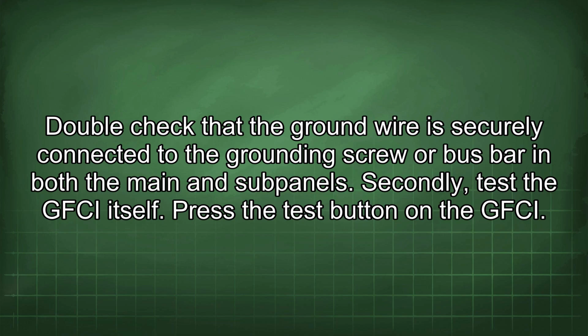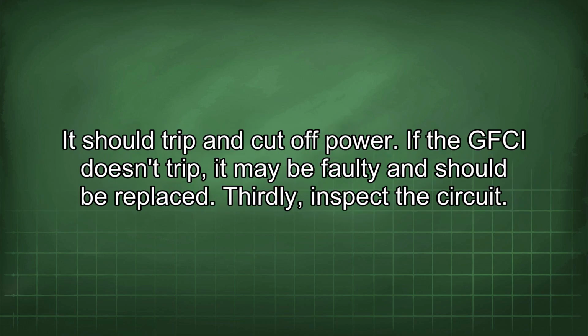Secondly, test the GFCI itself. Press the test button on the GFCI. It should trip and cut off power. If the GFCI doesn't trip, it may be faulty and should be replaced.